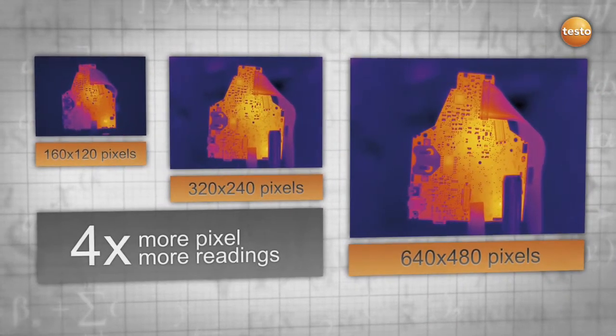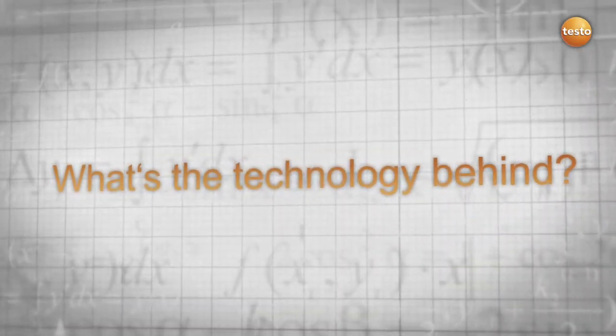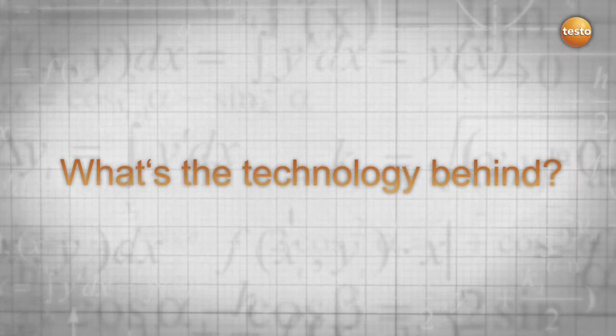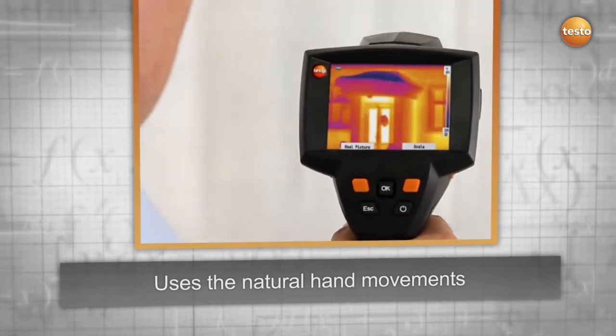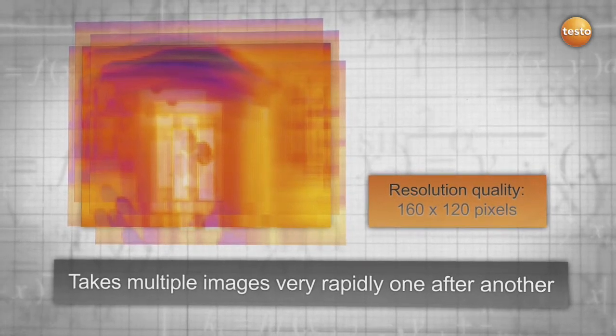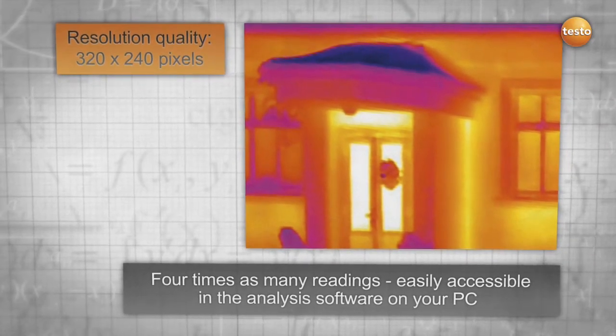The Super Resolution technology uses natural hand movement and takes multiple images rapidly one after another, which are slightly shifted to each other. Using an algorithm, these images are then calculated to obtain one image. The result: four times as many readings and a much better thermal image resolution.